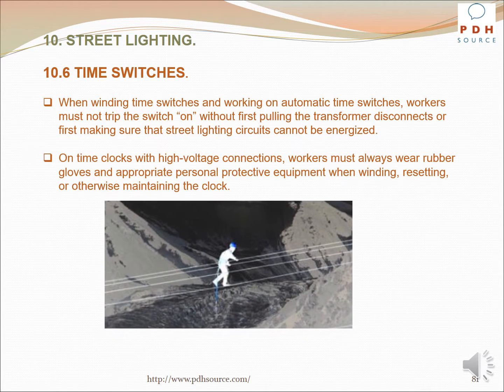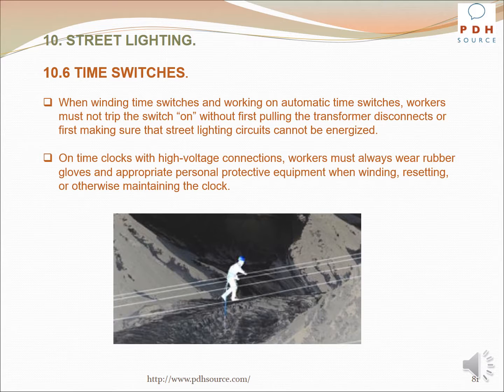When winding time switches and working on automatic time switches, workers must not trip the switch on without first pulling the transformer disconnects or first making sure the street lighting circuits cannot be energized. On time clocks with high voltage connections, workers must always wear rubber gloves and appropriate personal protective equipment when winding, resetting, or otherwise maintaining the clock.